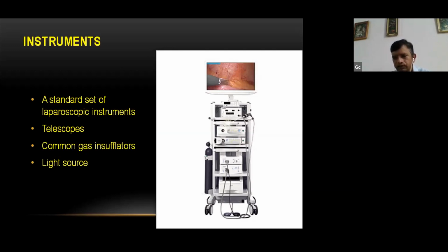So it removes all fumes from this closed space. That's why high flow insufflators, or high capacity insufflators like 35 liters or more, are required, like in bariatric surgery.